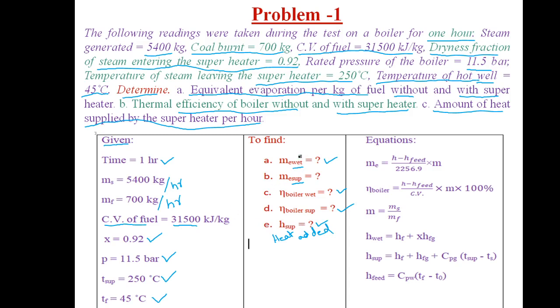The first column is given data, the second column is what we are supposed to find out. Before solving the problem we will make a plan. For equivalent evaporation, the formula is: (h minus h_feed) divided by h_fg — that is latent heat of vaporization 2256.9 — multiplied by m, where m is the ratio of mass of steam to mass of fuel, ms divided by mf. The second equation for boiler efficiency: boiler efficiency equals (h minus h_feed) divided by CV, where h is the enthalpy of steam coming out of the boiler and h_feed is the enthalpy of water entering the boiler.